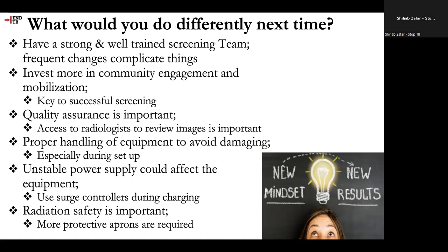And proper handling of the equipment is needed to avoid damaging it, especially during setup. People have to be calm and set up carefully so that you don't have equipment falling out of your hands. And then unstable power supply is common in this area, so there's need to use surge controllers, because recently we lost one of our power packs. But thanks to Stop TB Partnership and the manufacturers, they were able to quickly mobilize and send us a new power pack to continue our screening.